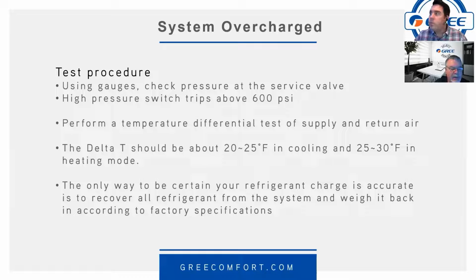And then, the only way to really be certain about your refrigerant charge, 99.9% certain, is to recover the refrigerant and then weigh it back in according to the factory specifications and any line length that you may have added. The other thing, and Daniel mentioned this morning, is when you're recovering refrigerant, let's say you're going to pump a system down and recharge it, weigh it out as well, so you can determine if the system was charged correctly. And then you already know what you're dealing with before you even start the evacuation process.